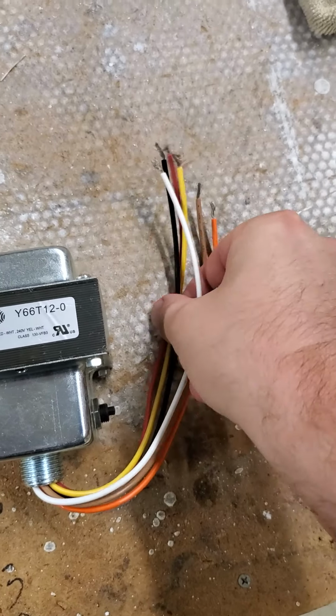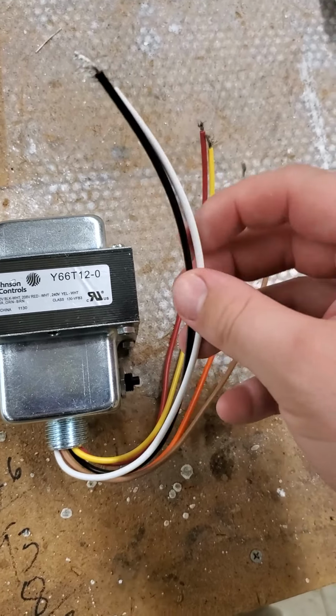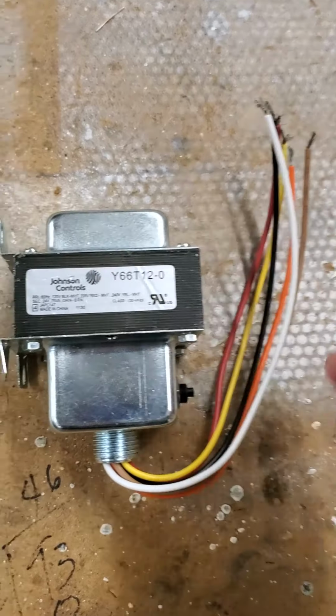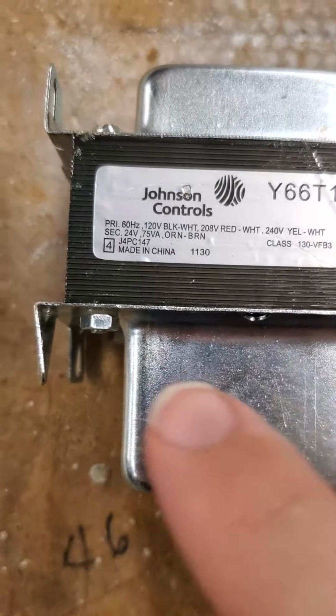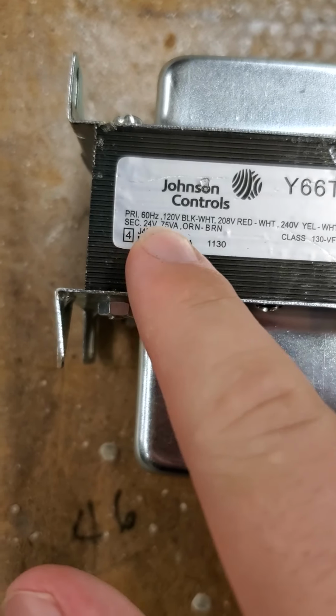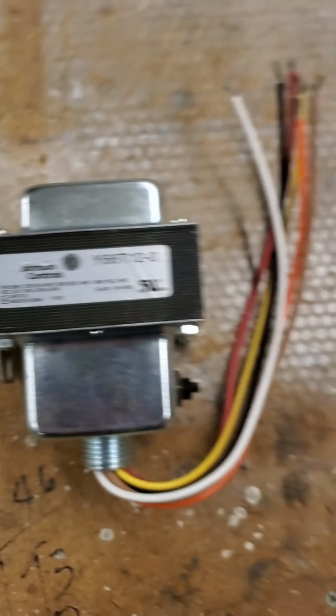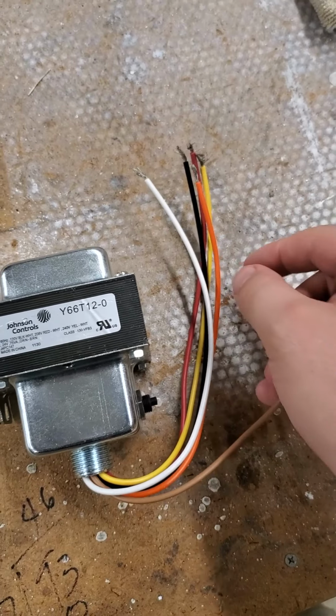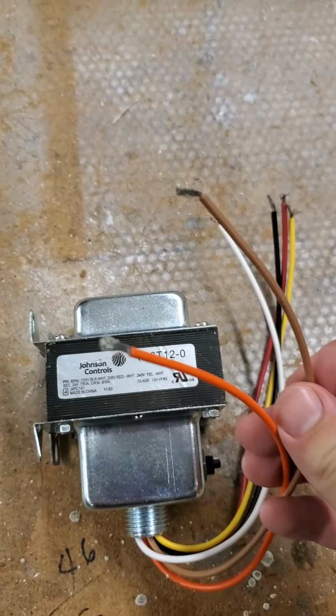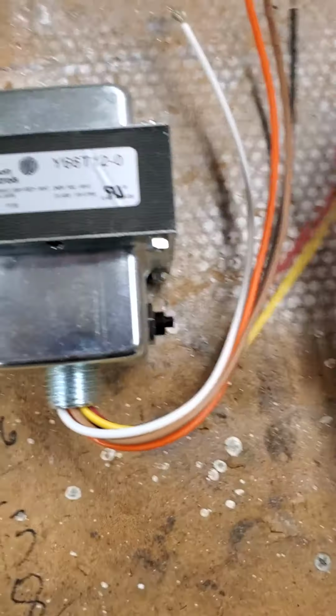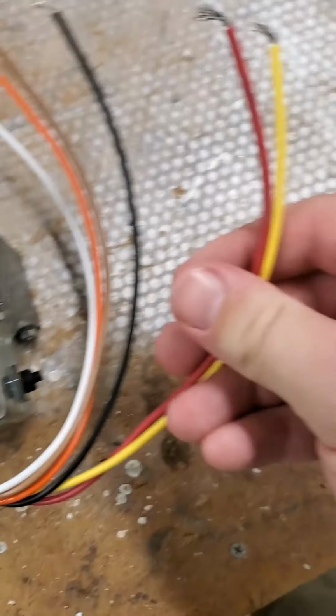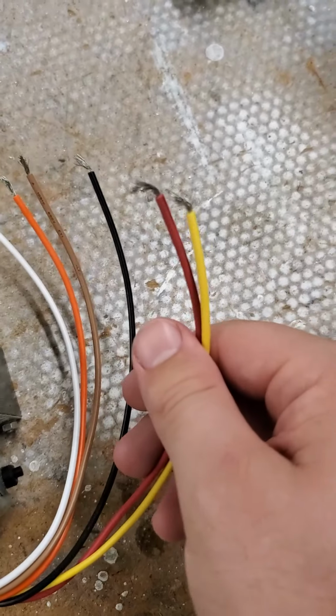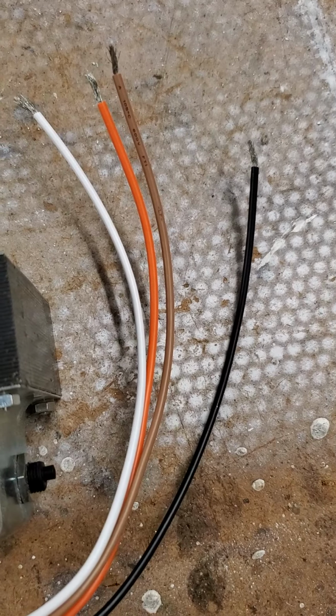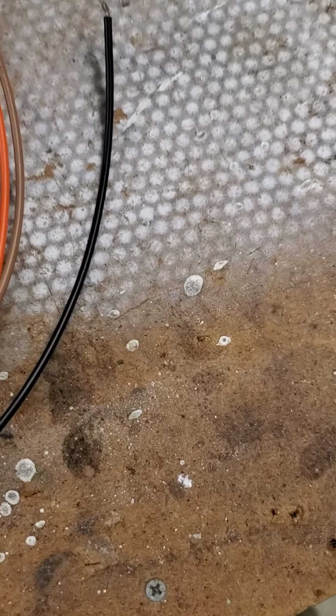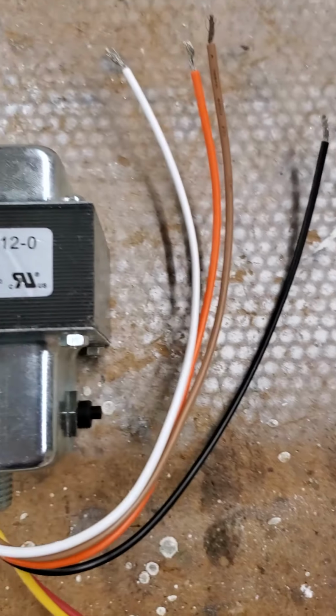So here I'm just showing the wires to you. That would be our 120 right there. Black and white, I'm pointing at it right now. 120. That's what you would normally use. And then the other two important ones are the 24 volts, which go to the actual controller. Okay, and then these last two, the red and the yellow, are used for 208 and 240, and they are not used, so it's just those four that you need for this. Wire up all 4 of those, and you've got power.